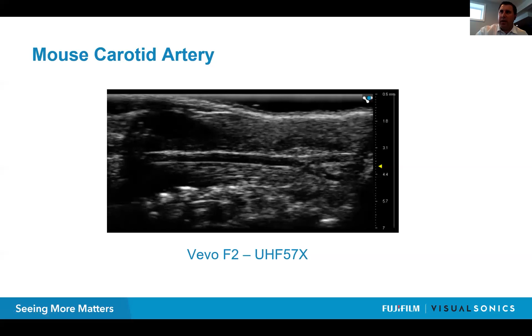So what we are doing here is really pairing together high image quality with access to very, very low level data. And I'm going to take you through how that low level data is acquired using the data interface. If you think of the transmit signal chain on our system, I'll show you some screen captures in a moment, but this is the Vevo F2 user interface. We now have the ability to configure all of the transmit and receive configuration. This is really the pulse sequence properties that allow us to set up the sequence of transmit events. We then have the ability to control the transmit pulser itself. This allows us to configure and shape the timing of the ultrasound pulse on a given channel. We also have the ability to set the voltage rail associated with that pulser. These are things that can all be done on the platform through a graphical user interface, and we will show you some of the captures of that shortly.